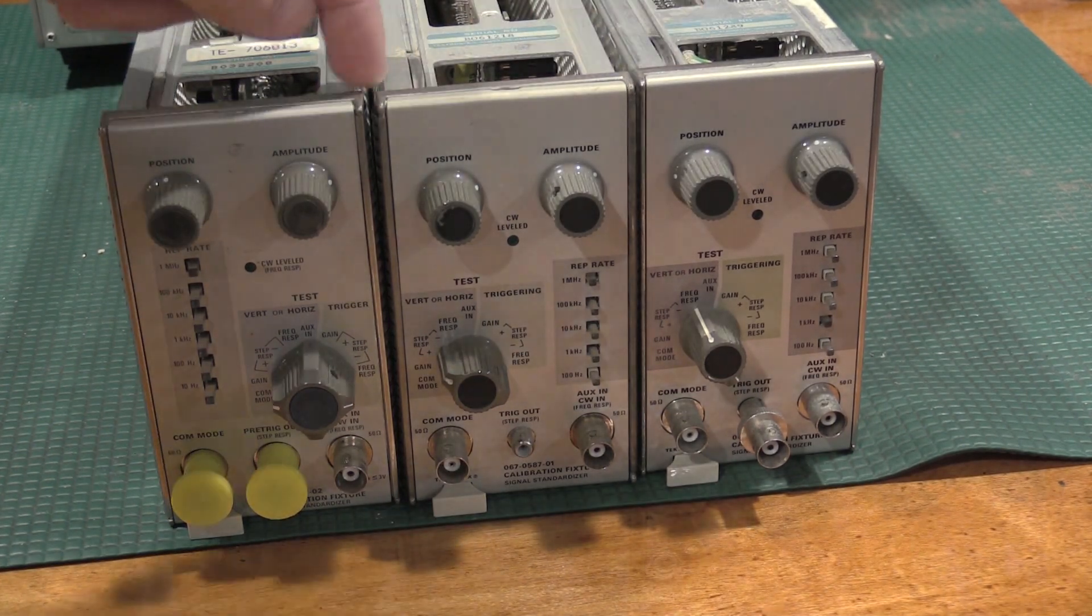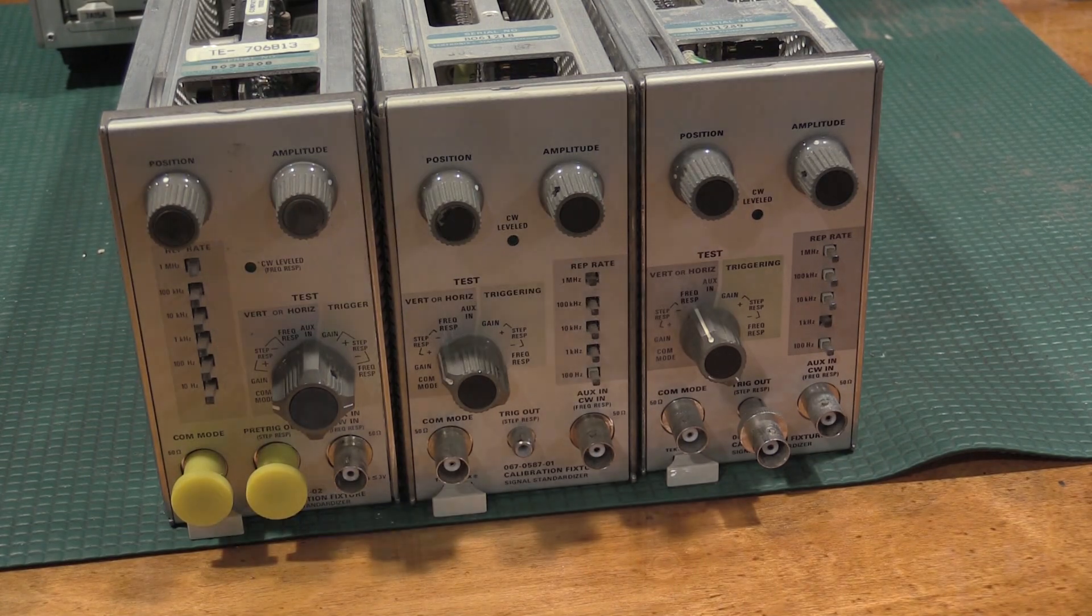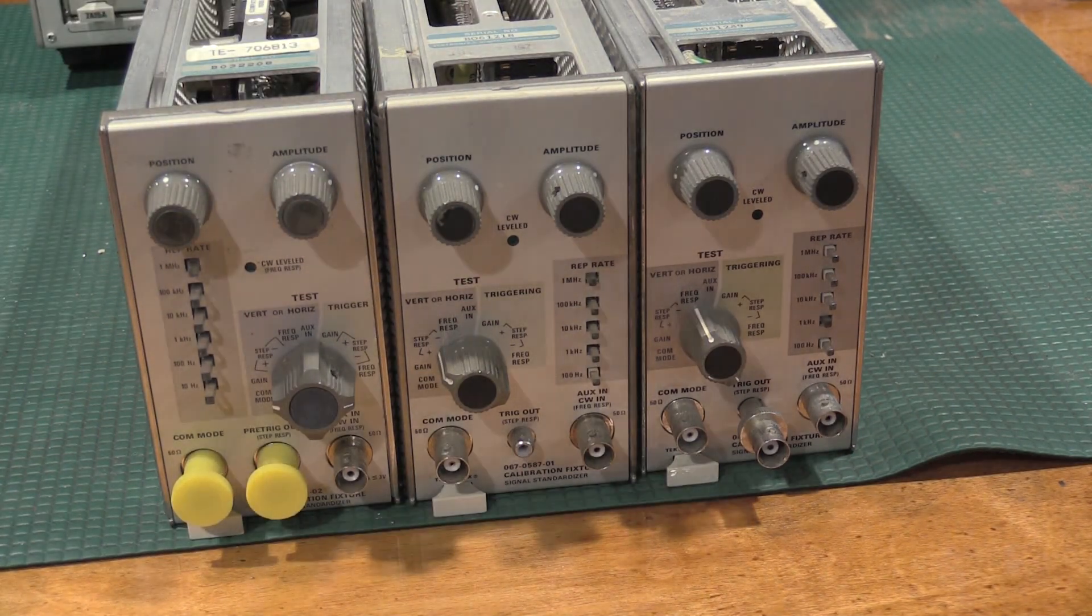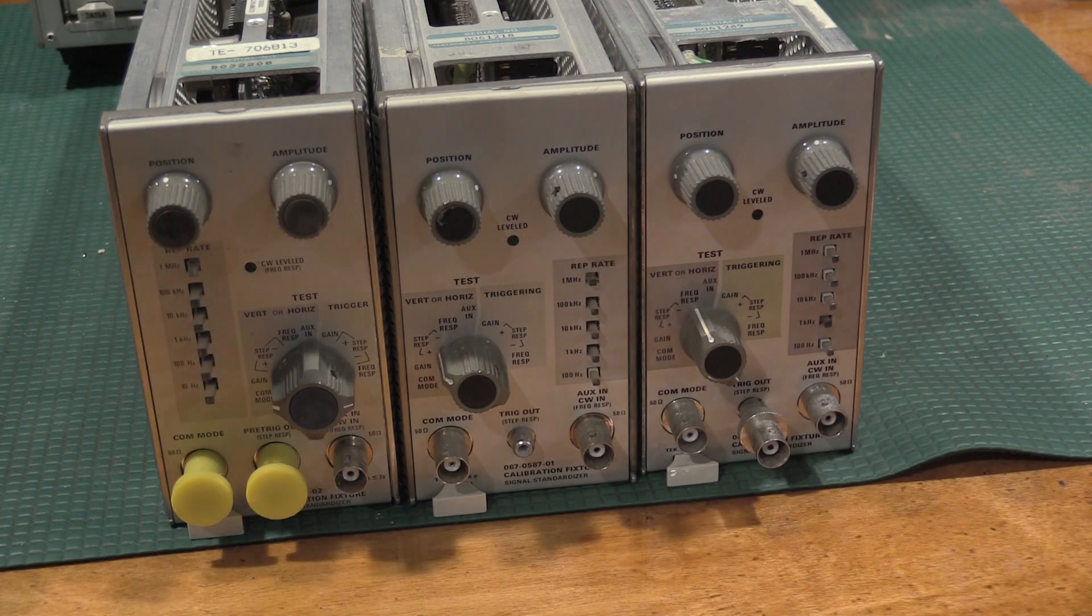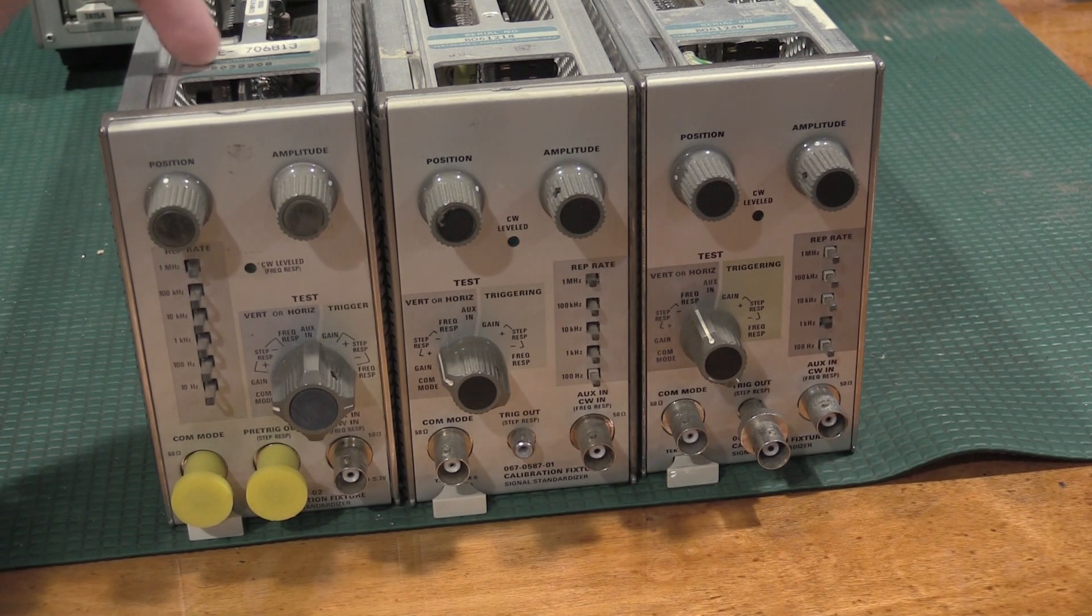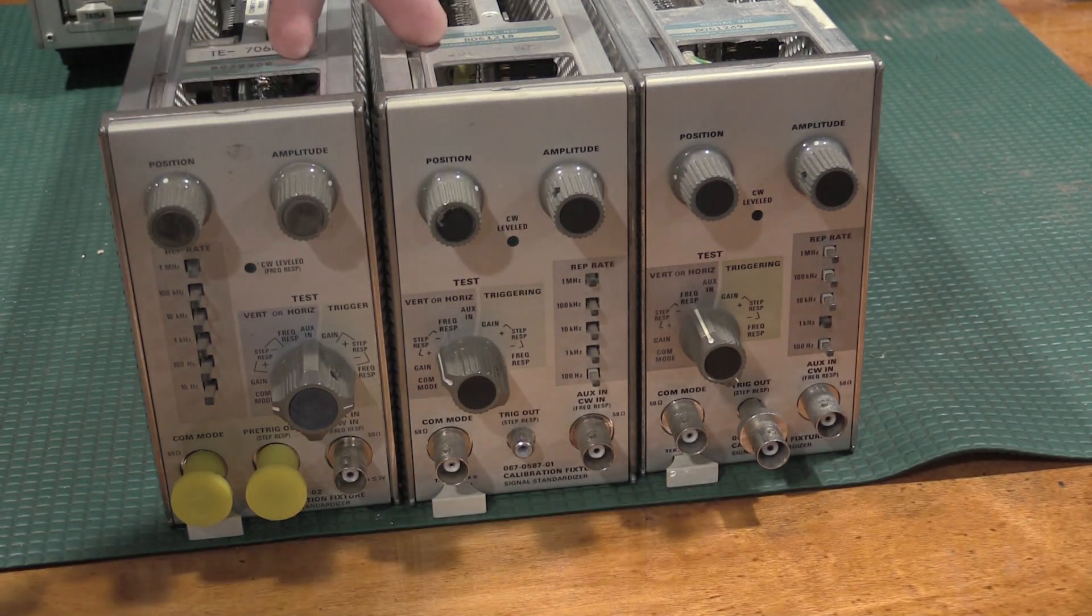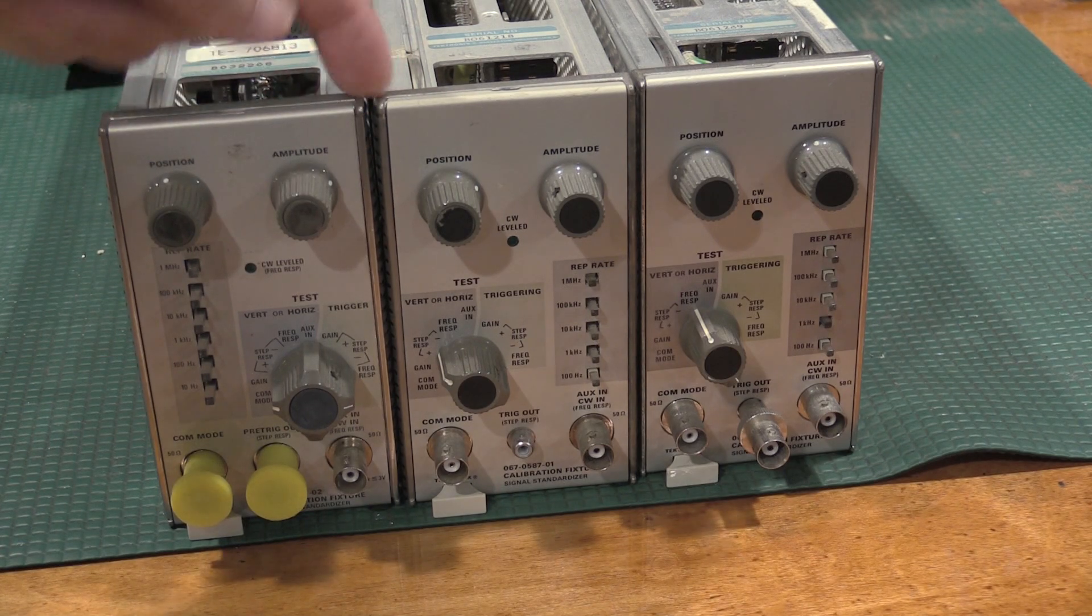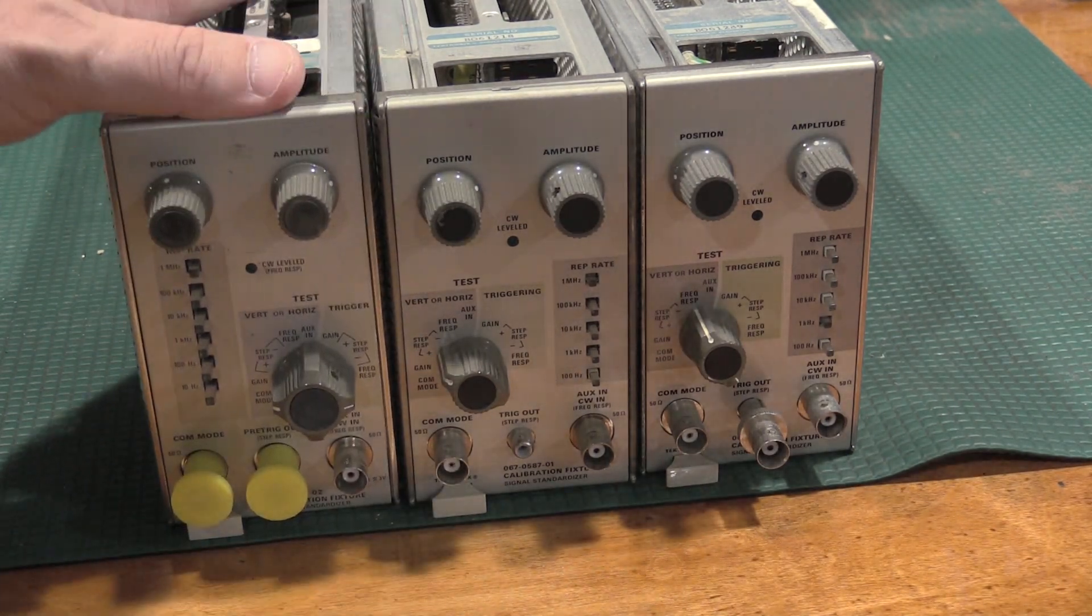If you have two of them, you can put one in a vertical bay, one in a horizontal bay, and you can make a dot matrix pattern on the tube. And that very much helps with an alignment. I'll show that a little bit later in the video. Dash 02 is good for anything in the 77 series and under for sure. You can really use them for the 7854 and maybe even the 7904. It's pushing it on the 7904. The 79s and the 71 scopes are what the dash 02 is designed for. They're the one gigahertz frames. So I used both of these for the 7904A when I checked it in. And I know the service manual calls for both of these for the 7854. So we'll be using the two of those. That's actually why I had to get the faster plug-in.